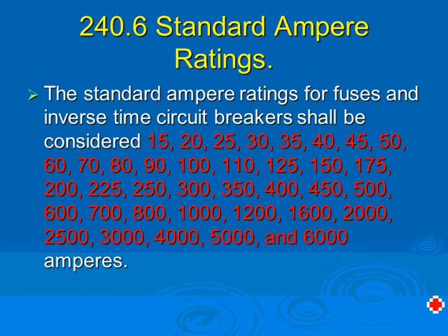So these are small conductors. I want to remind you, this says fuses and breakers shall be considered. These are fixed circuit breakers and fuses. The standard sizes of fixed circuit breakers and fuses go from 15 all the way to 6,000 amp. The most utilizable ones are 15 to 3,000. 4,000, I have a few projects. I've never done anything higher than 4,000. Anybody have done anything higher than 4,000?